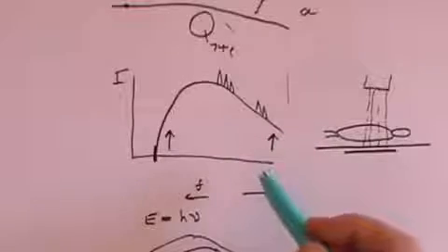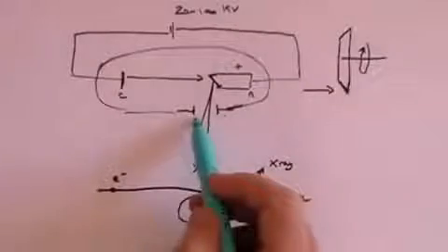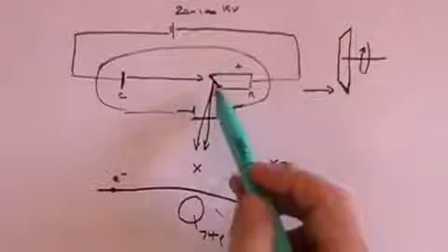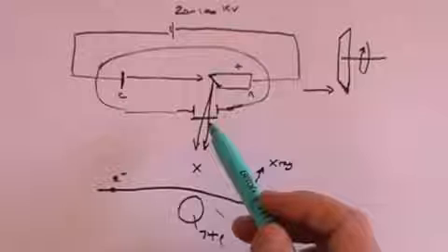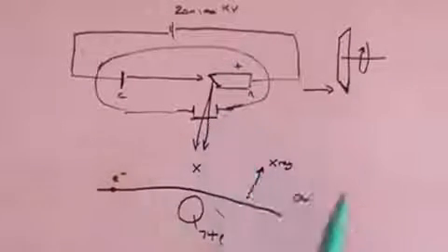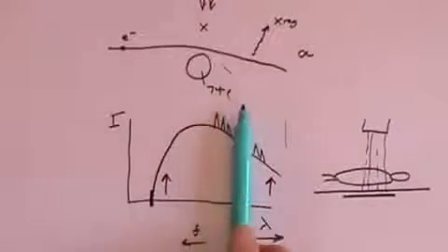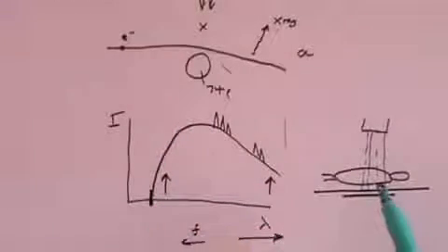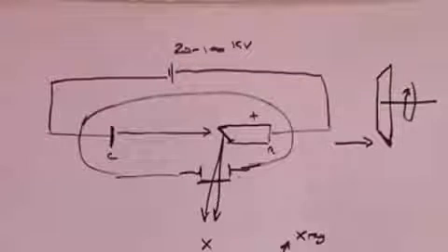And so typically the way that you get rid of those is you put an aluminium plate across the exit of the X-rays, and that aluminium plate will take out all the low energy X-rays that would never penetrate the body, so that you've only now got the, as it were, high end of the X-ray spectrum, and that has got the energy to penetrate and hit the photographic plate. There is a further option here.